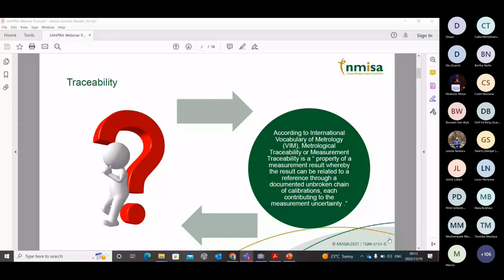The thing that we need to start with is to ask ourselves, what is this term traceability? Metrological traceability, in short traceability, according to the International Vocabulary of Metrology, is a property of a measurement result whereby the result can be related to a reference through a documented unbroken chain of calibrations, each contributing to the measurement uncertainty.